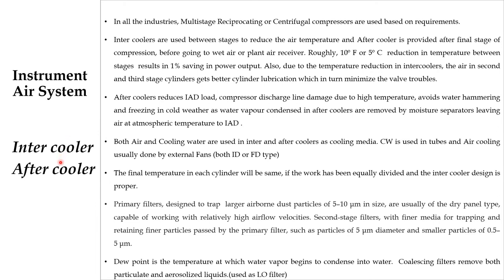Now we can see about the intercooler and aftercooler. In all the industries, multi-stage reciprocating or centrifugal compressors are used based on requirements. Intercoolers are used between stages to reduce the air temperature, and an aftercooler is provided after the final stage of compression, before going to the wet air or plant air receiver. A roughly 10°F (5°C) reduction in temperature between stages results in 1% saving in power output. Also, due to temperature reduction in intercoolers, the air in the second and third stage cylinders gets better cylinder lubrication, which in turn minimizes valve troubles.